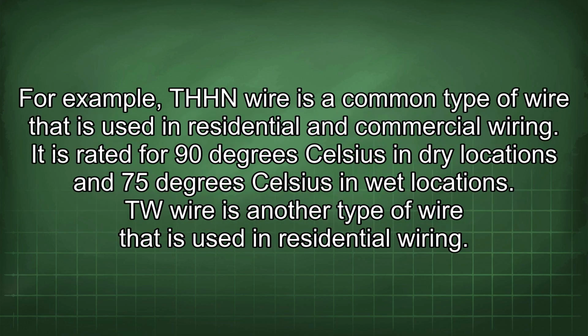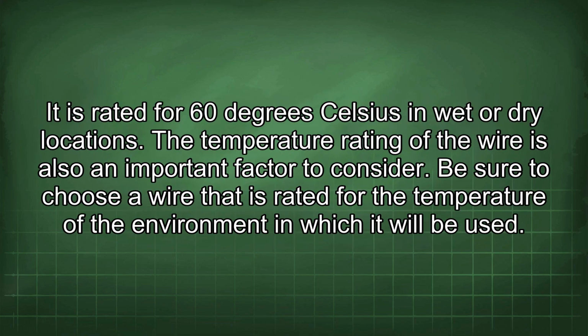For example, THHN wire is a common type of wire that is used in residential and commercial wiring. It is rated for 90 degrees Celsius in dry locations and 75 degrees Celsius in wet locations. TW wire is another type of wire that is used in residential wiring. It is rated for 60 degrees Celsius in wet or dry locations.